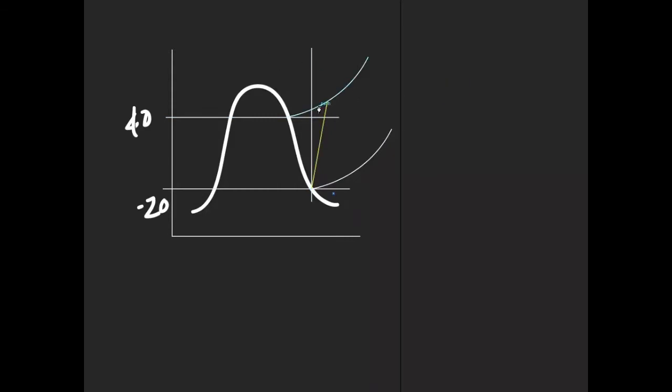So we would compress from the low pressure at suction up to the high pressure, and of course it comes out at some higher temperature because of the heat of compression and the inefficiencies, but we run that through a cooling water exchanger at the high pressure, so that cools down the superheat, and then if you continue to cool it, you'll bring it down to the saturated liquid line on the left side of the dome.